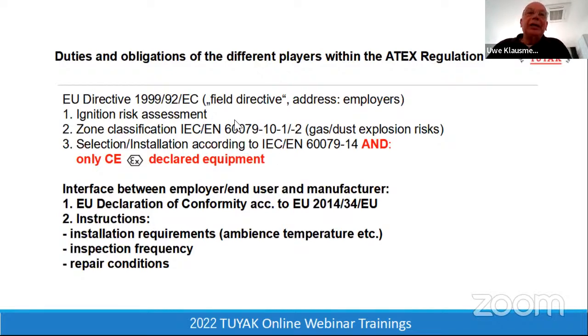After you have made this exercise with these standards, which is really complex to conduct, it means you have to make calculations, assume leakage situations, assume ventilation in your location, which could be in the mountains or at the coast. Wherever it is, you need to assume which ventilation you can assume, and so on. Many parameters you have to put in the calculation so that you can finally say, this is zone 0, this is zone 1, and this is zone 2.